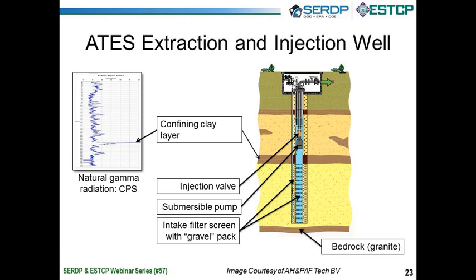If we're in the injection mode, the water comes back down that same well, travels down through here, hits a check valve at the pump discharge and cannot backflow into the pump. There's an injection valve I'll show you a close-up on later. It opens up, lets the water into the well, and the water flows back into the formation basically by gravity. So that is the fundamental difference between a traditional water well and a geothermal well, in that our wells can function both as supply wells and injection wells.